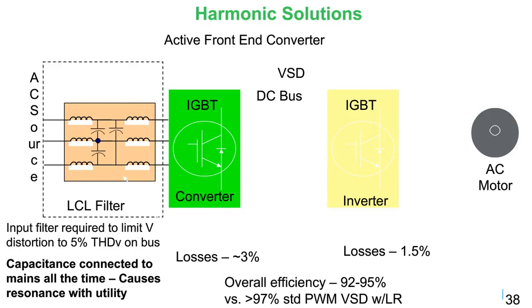And additionally, there is capacitance always attached to the AC mains, even when the VFD is powered down. This is known to cause resonance on utility substations. And in fact, in a couple of cases, one I'll share with you in a few more minutes, the LCL filter actually caught fire. Again, we'll discuss this in more detail in a few minutes. But essentially, what I want to point out here at the bottom left is a capacitance connected to the mains at all times, so this can cause resonance on the utility even when it is powered down.